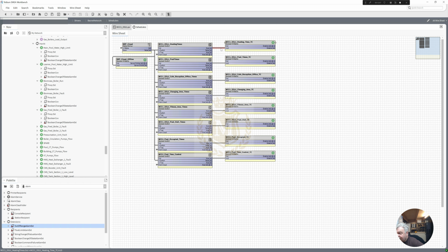When we've got the connection, we will use the time clock from the cloud server that we've done, and it will pass that information through. So it would disable itself at night time if it's required. One of them will be 24/7, which will be the pool time control. You never stop the pool. You never want to stop the pool heating. But the other areas you can stop when it's actually out of times. So that's how we do that.